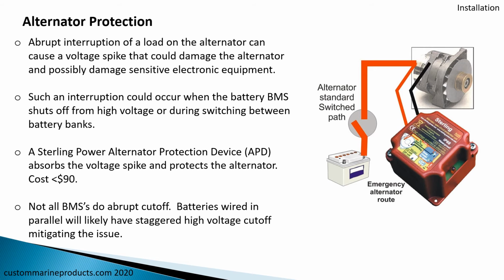Now, not all BMSs do this abrupt cutoff. And another thing to consider is if you have a number of batteries wired in parallel, they're not going to all shut off instantly at the same time. Now, the shut-off time we're talking about here is in seconds or tenths of a second, not a long period of time, to give the alternator time to shut down without a voltage spike. So in a group of batteries, let's say our 4 batteries are wired in parallel, each one is going to shut down as it reaches its peak voltage. The last one would be the amount of shock, if you will, to the alternator, which would be relatively minor.